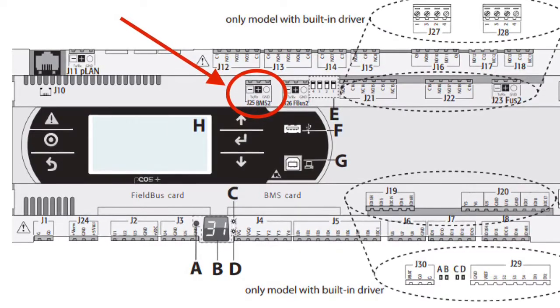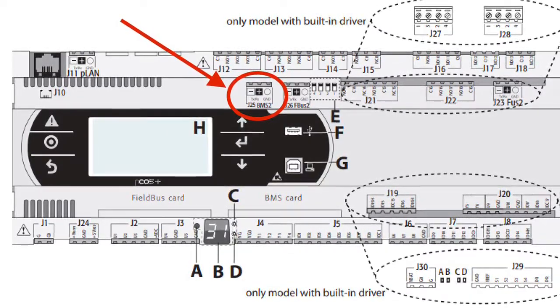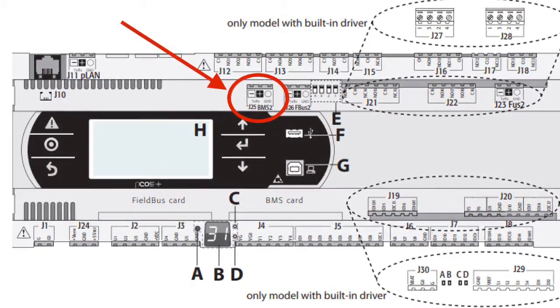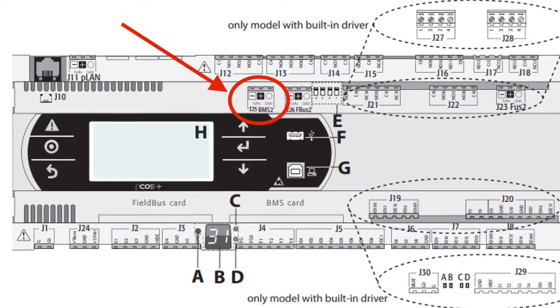The pCO5+ controller is equipped with a built-in RS485 serial port, typically used to connect via Modbus protocol to a BMS. This is labeled on the controller as J25 BMS2.